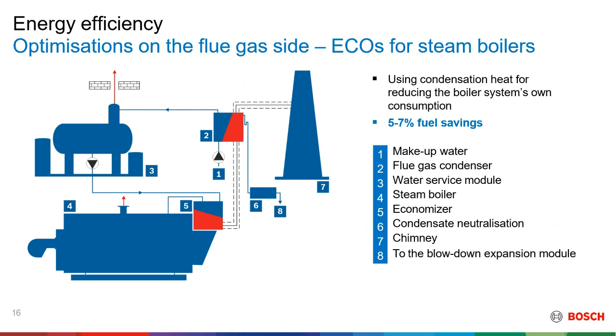Here you're saving around 5 to 7% of fuel just by picking up the extra heat from the flue gas. The difference from the normal economizer is that the condensing economizer uses water that is flowing into the feed water tank, while the normal economizer uses water that is flowing into the boiler. Next slide.